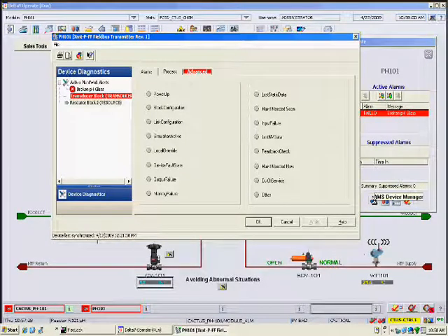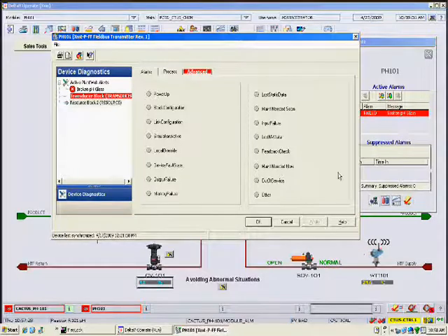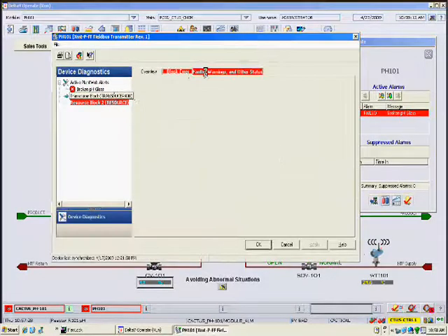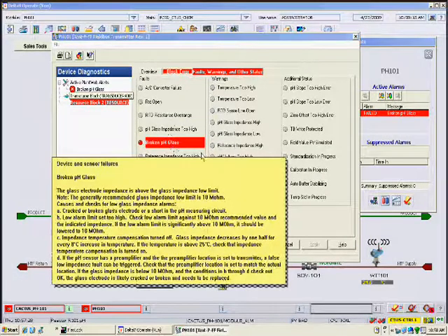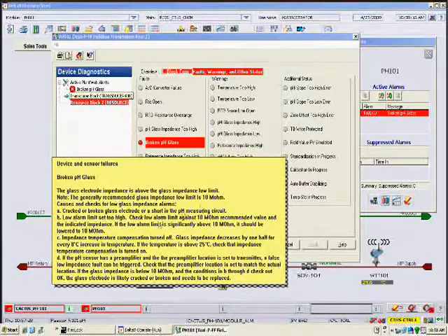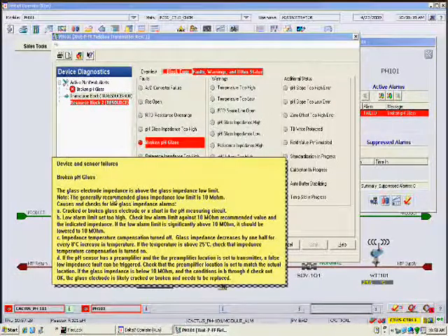There is no need for the technician to move to another maintenance computer, login, and search for the tag. The operator follows the red tabs to see the details of the failure. The content and structure of the diagnostics display is completely controlled by the device manufacturer using EDDL, not the system manufacturer.